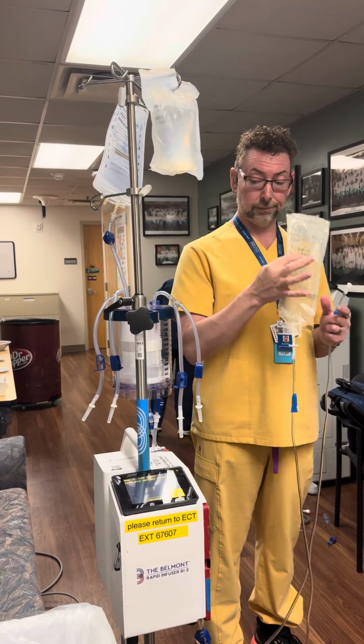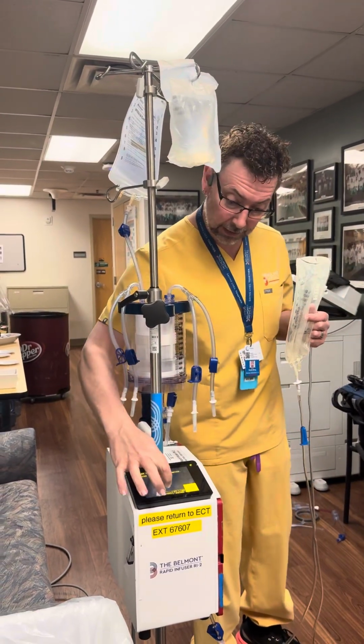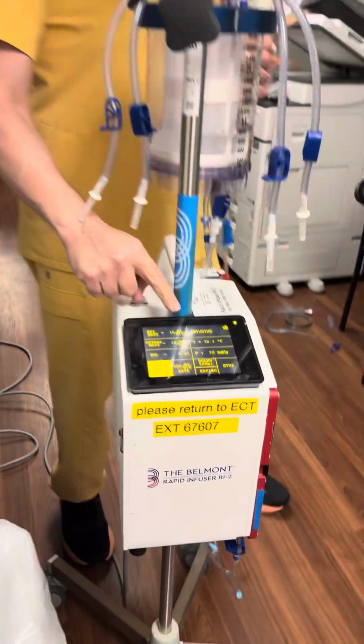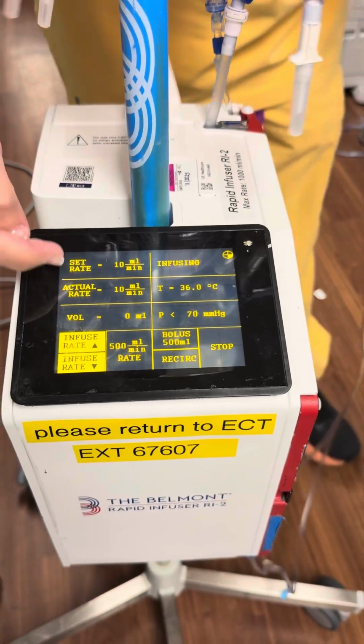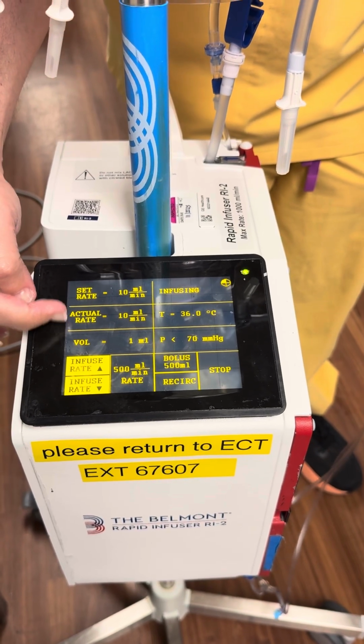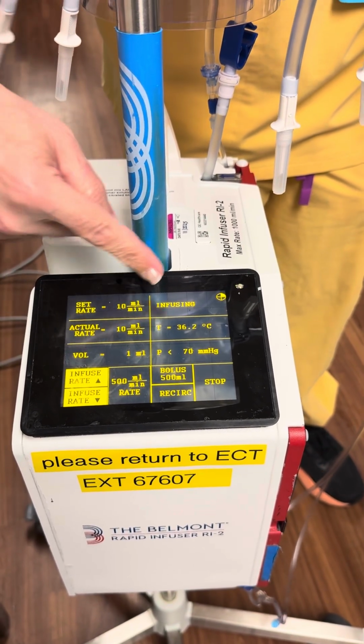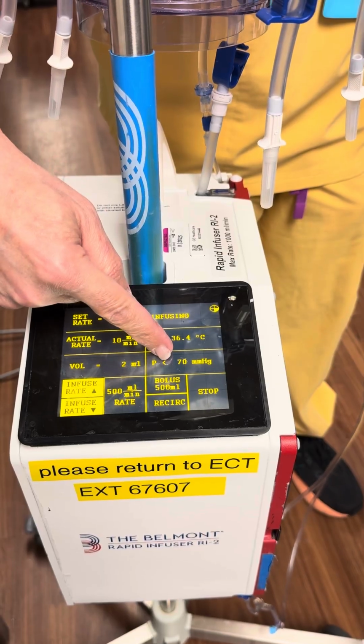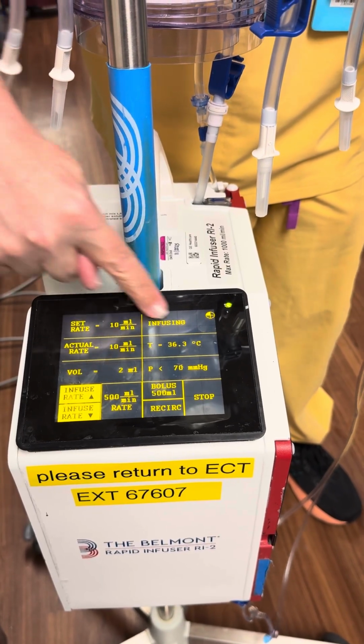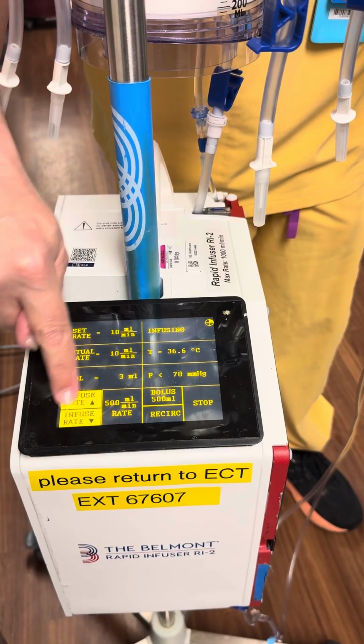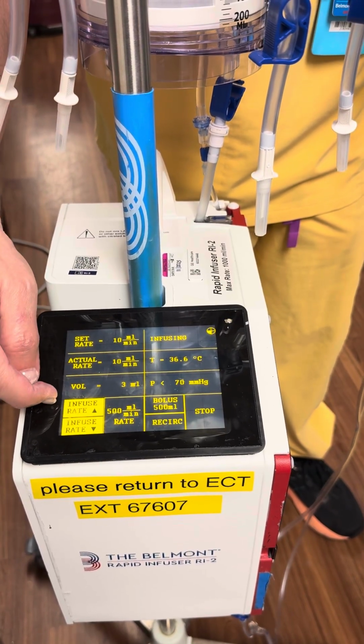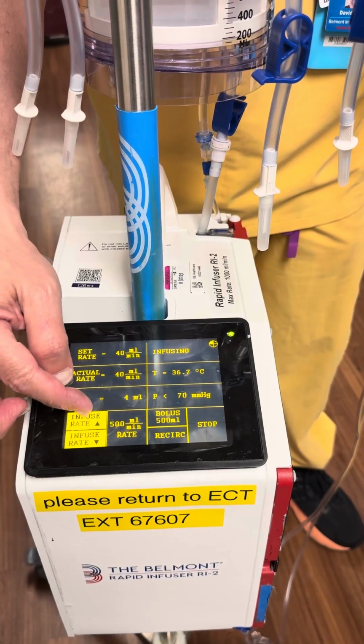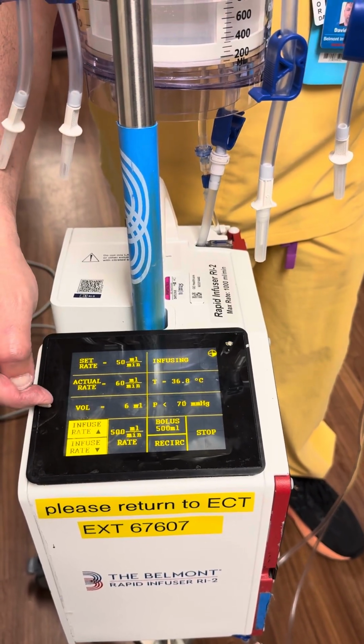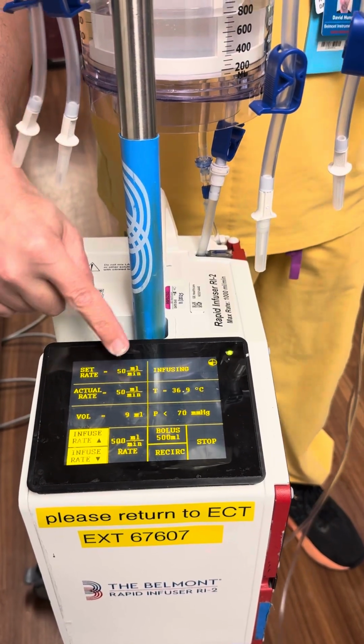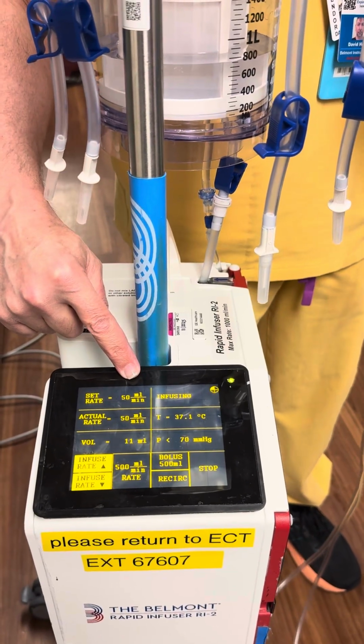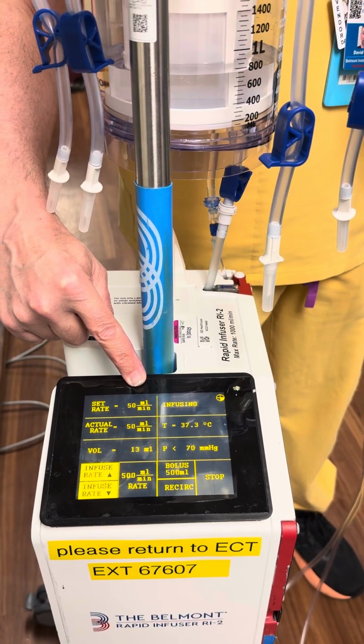Once you're connected to your patient, spike the blood, hit infuse, and the system defaults you automatically to 10 milliliters a minute. Set rate is what you've asked for, actual rate's what you're getting, and the volume is how much you infused into the patient. Then the system shows what it's doing, the temperature being delivered, and the back pressure from the patient's catheter. These top 6 boxes are your information. These 3 keys are how you change your flow rates. Arrows give you the ability to change in 10 milliliter increments. So if you're needing to make small changes, you can do up or down with the arrows and it changes in 10 mils. Just always remember this number is minutes, not hours. So at 50 milliliters a minute, you're giving your patient 3 liters an hour.